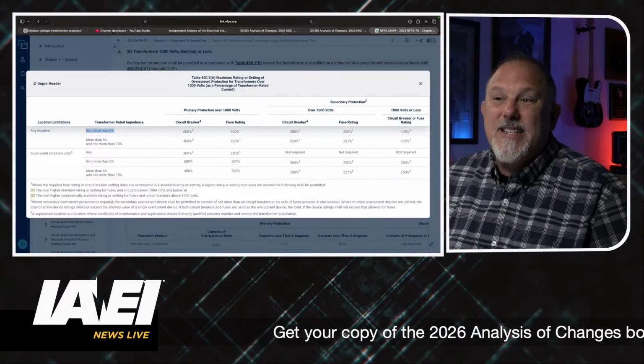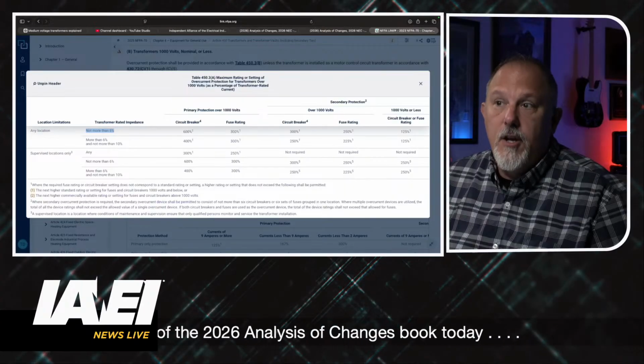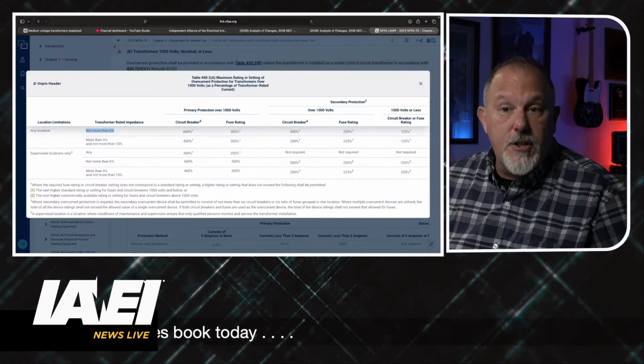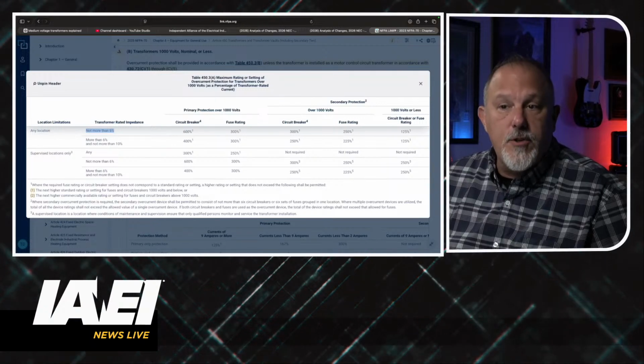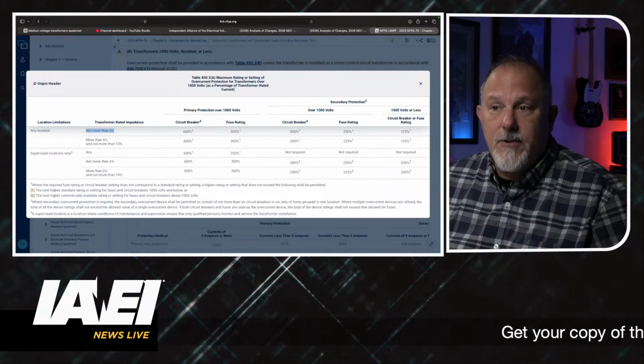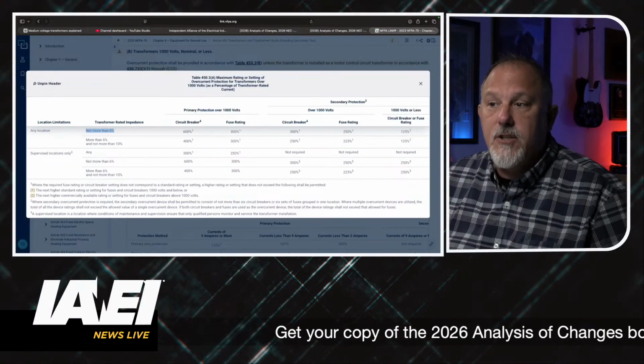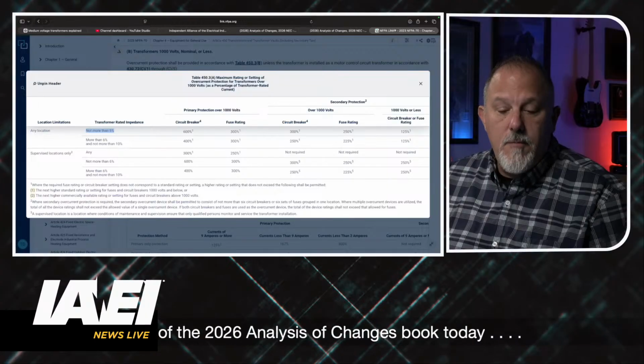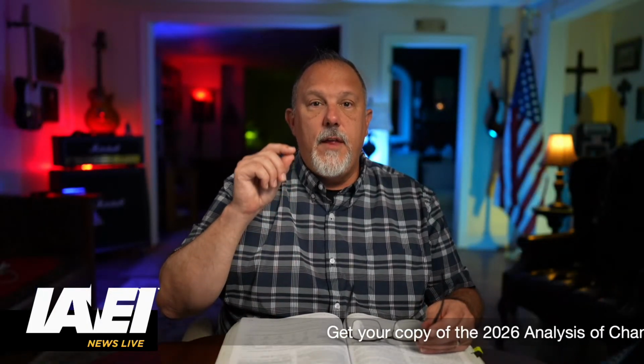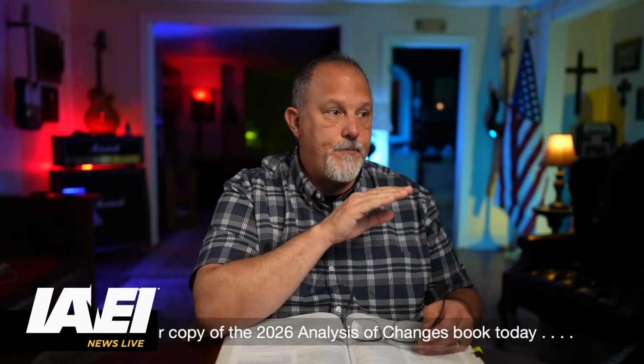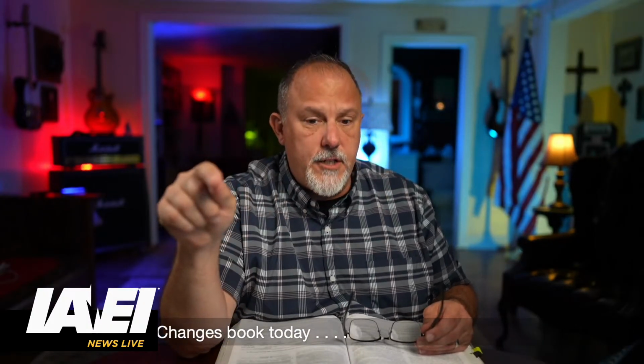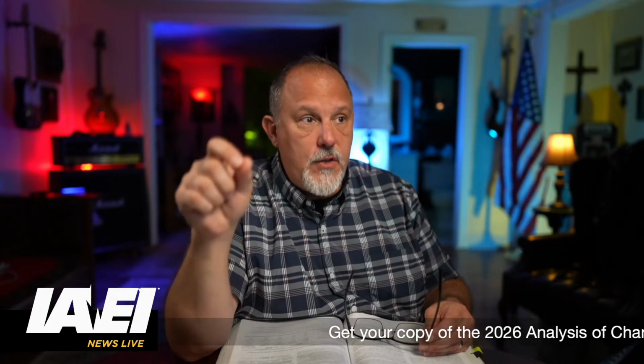for a circuit breaker, I can go up to 600% on the primary. For a fuse, up to 300%, and there's a note 1 where the required fuse rating or circuit breaker setting does not correspond to a standard rating or setting, a higher rating or setting that does not exceed the following. So remember, in low voltage applications, I could not exceed this maximum rating. What they're telling me for medium voltage, they're putting me up to 600% on the primary and 300%, 600% for breakers, 300% for fuses.